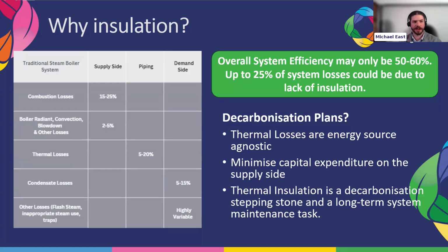But it's important. If we have a look at the table on the side there, this is a traditional steam boiler system. Chris alluded to this at the start, and Elsa touched on it as well with the condensate losses and flash steam. But a traditional steam boiler system could only be 50 or 60% efficient, and up to 25% of the system losses could be from a lack of thermal insulation.